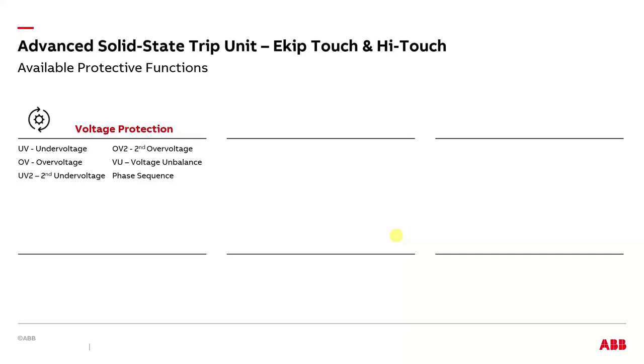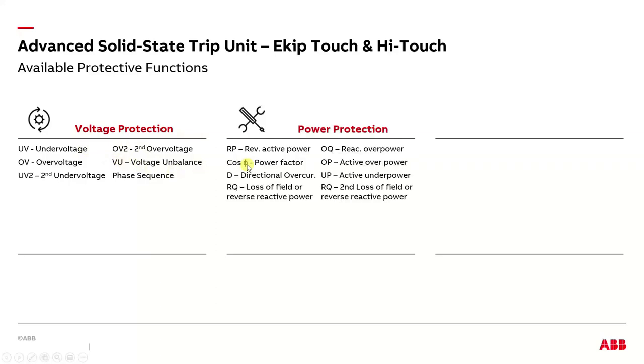This is just to give you a flavor of some stuff you can now do with a molded case breaker that you couldn't do in the past. You can get this breaker with voltage protections, undervoltage, overvoltage. Typically, a lot of the protections have two levels to them, so you can either have a backup or you can switch in and out two different setting groups, phase sequence, power protections, reverse active, so reverse power flow, directional overcurrent. These are protective functions that you've never seen in low voltage breakers. These were reserved for protective relays. But now they're in the molded case and low voltage power circuit breaker market.